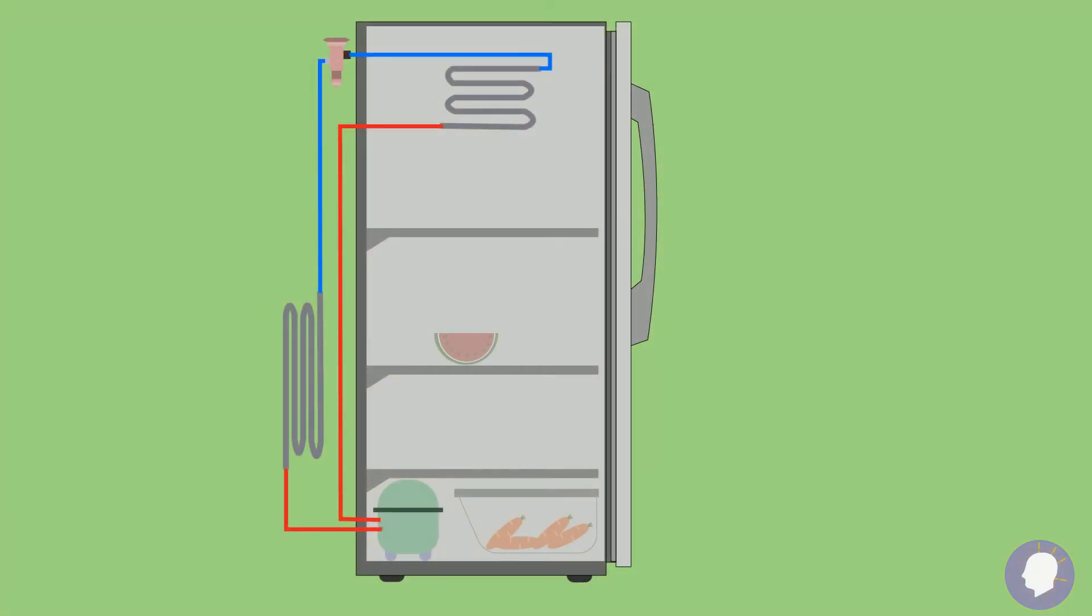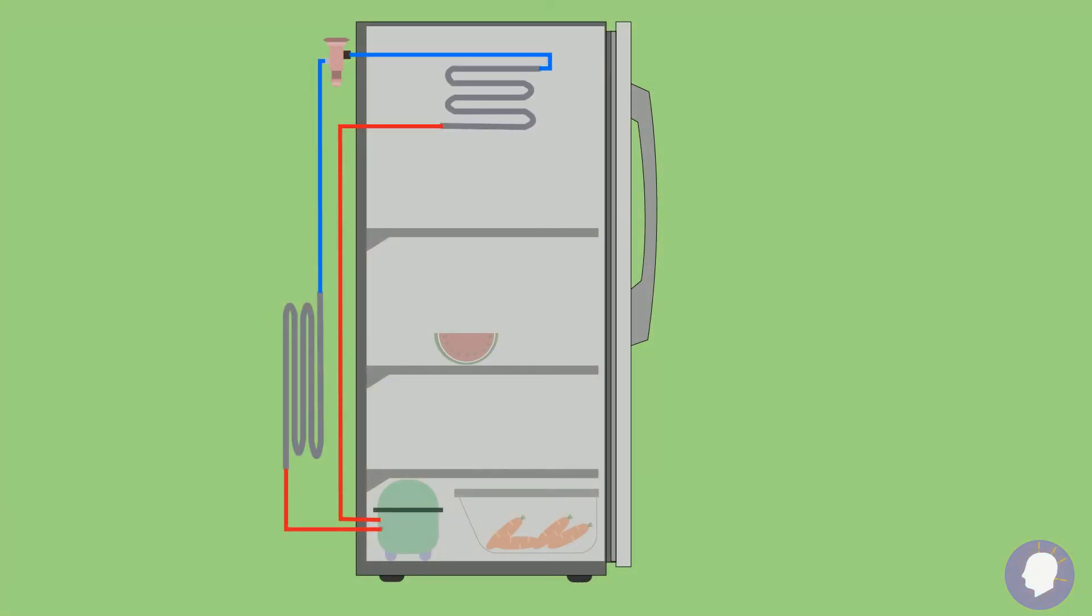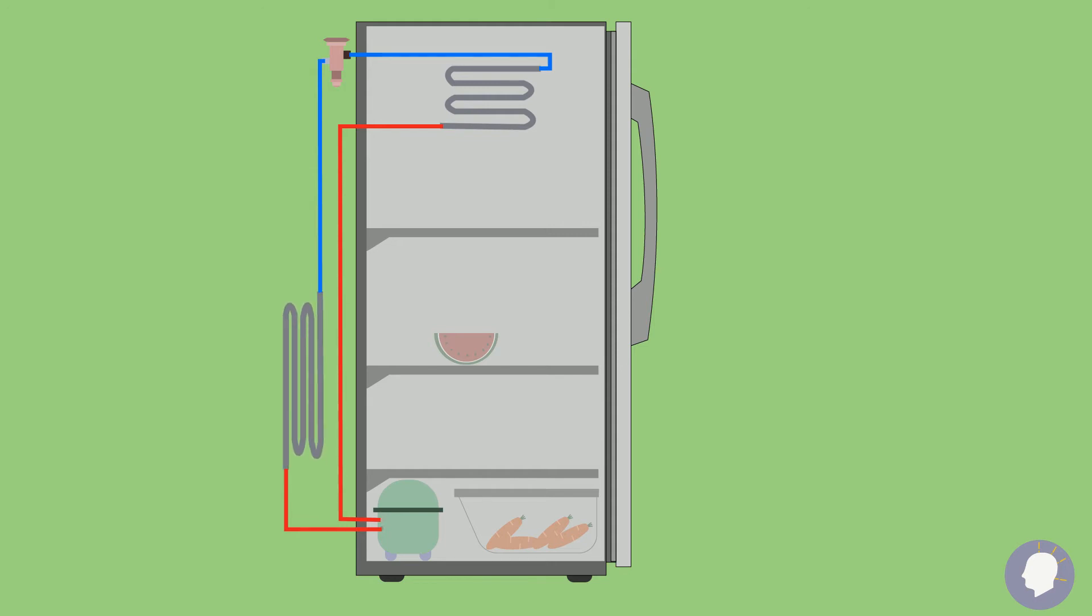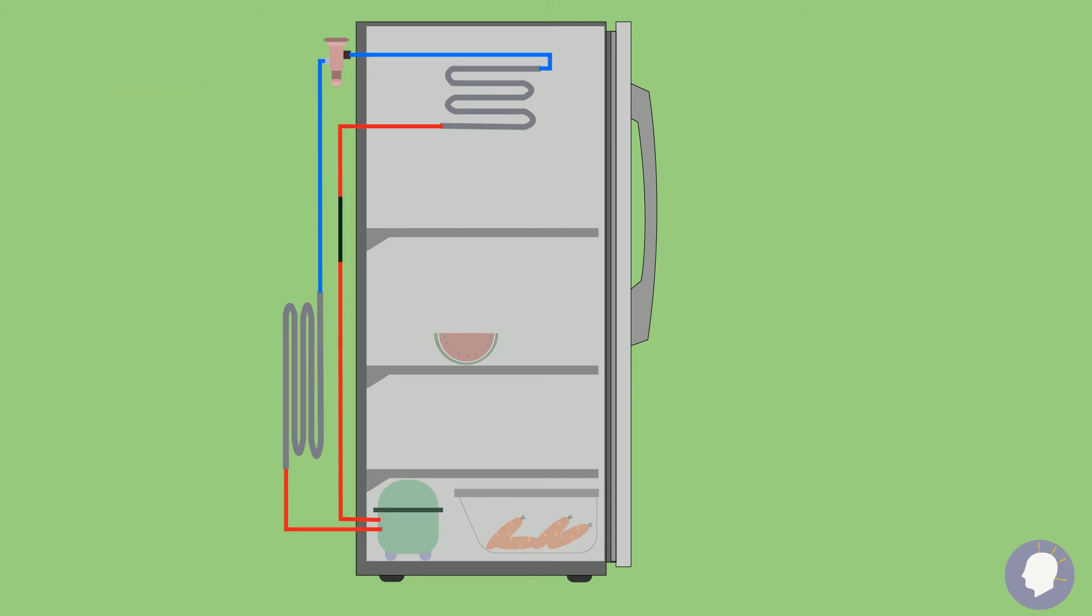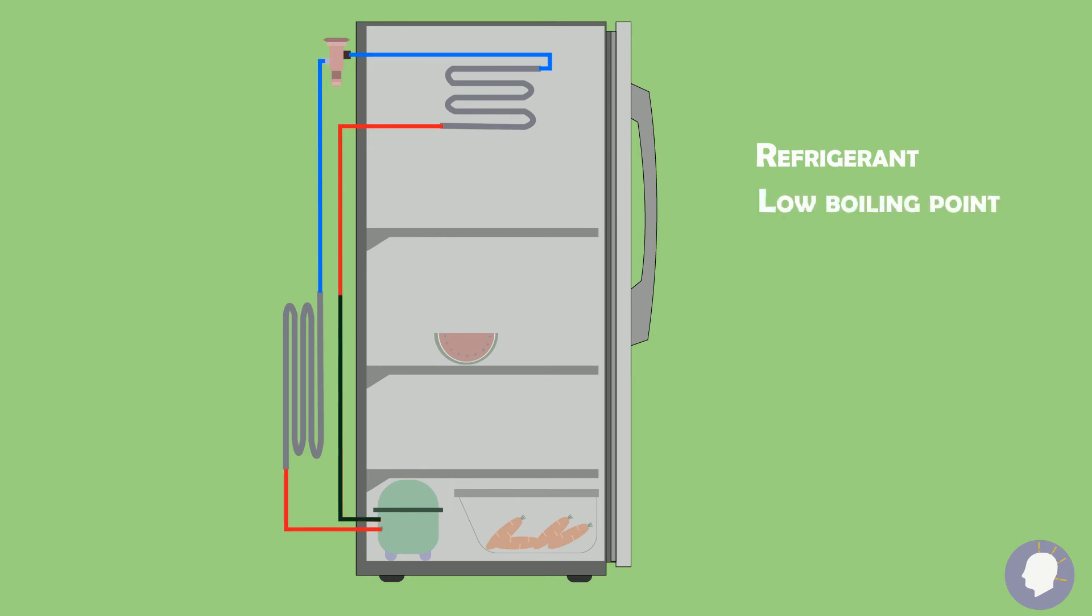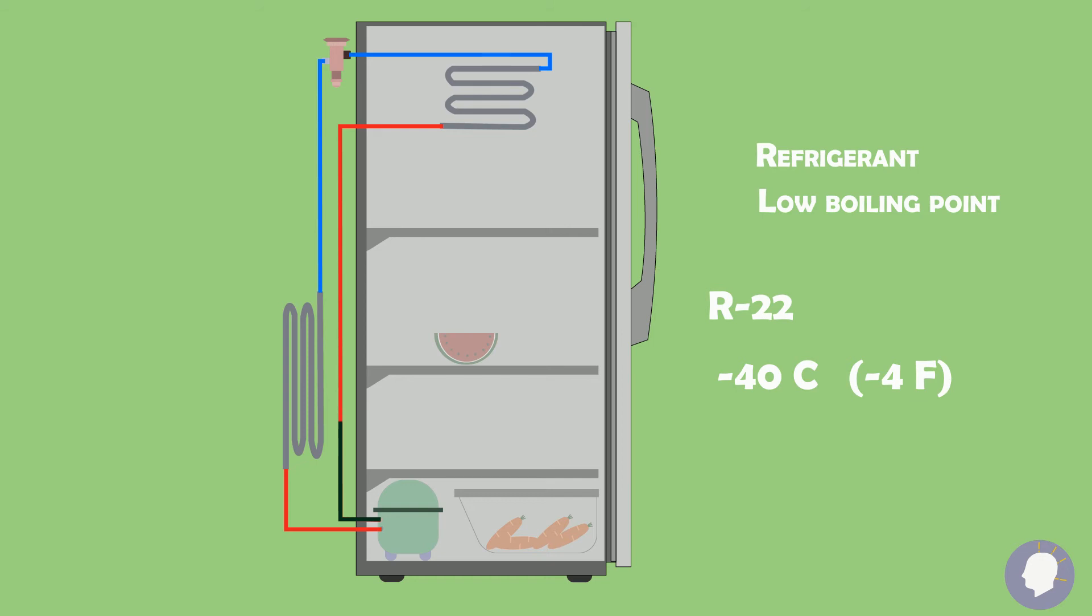So let's go over this again. We have a coil inside our box called the evaporator coil and one outside the box called the condenser coil. These two coils are connected using the suction line and liquid line flowing through the system is a fluid called a refrigerant. One important property for any refrigerant is to have a very low boiling point. R22, a common refrigerant, begins to boil at negative 40 Celsius. Yes, this fluid begins to boil at a really cold temperature.